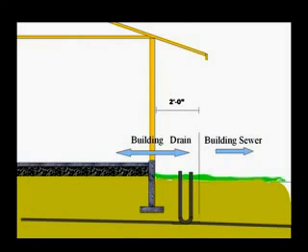The terms building sewer and building drain are used interchangeably but are quite different. The building drain is the waste piping inside the building to a point two feet outside the building. The building sewer begins at a point two feet outside the building and continues out to the street.